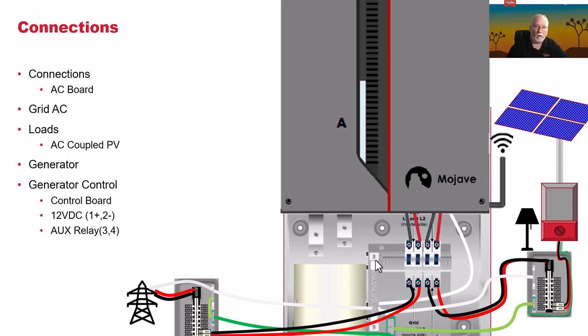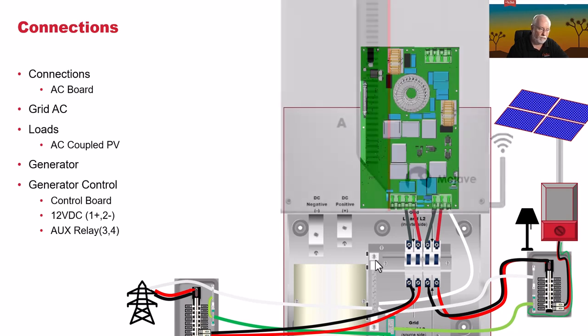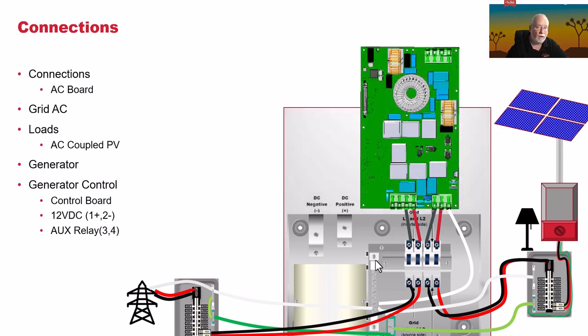Now let's talk about if we wanted to hook up a generator. First thing we want to do is remove the top cover. There's 4 screws. It's not a Radian. They're not a ton of screws. It's actually just 4 5mm hex bolts. Pull those out, take them out, and what you'll see is the AC board. There's already 5 connections there, right? 2 inputs and a neutral and 2 outputs.